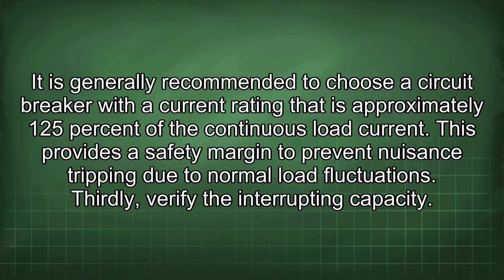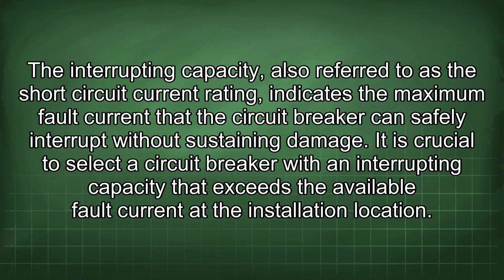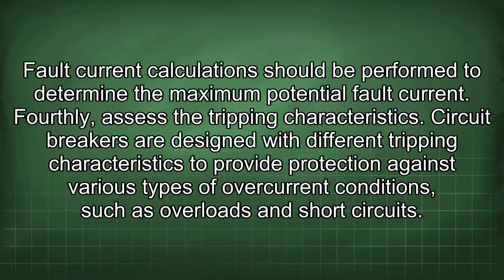Thirdly, verify the interrupting capacity. The interrupting capacity, also referred to as the short circuit current rating, indicates the maximum fault current that the circuit breaker can safely interrupt without sustaining damage. It is crucial to select a circuit breaker with an interrupting capacity that exceeds the available fault current at the installation location. Fault current calculations should be performed to determine the maximum potential fault current.